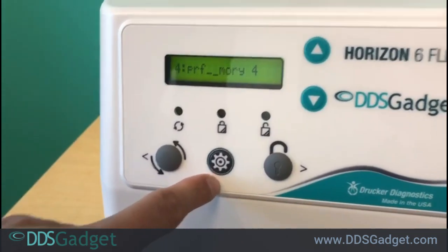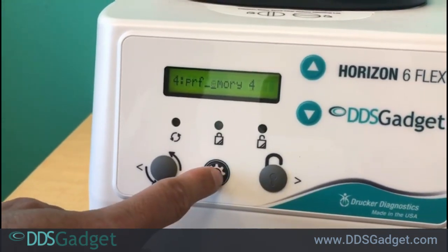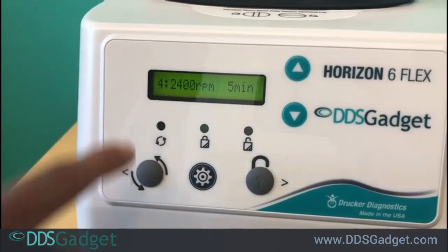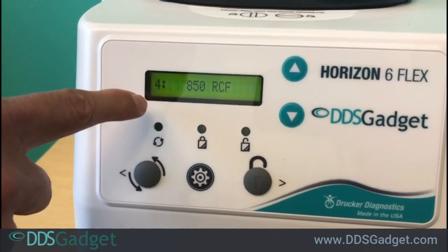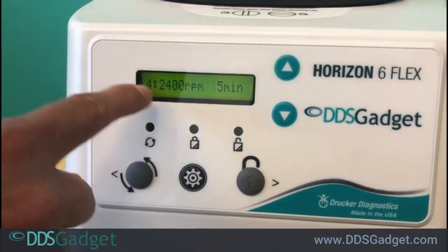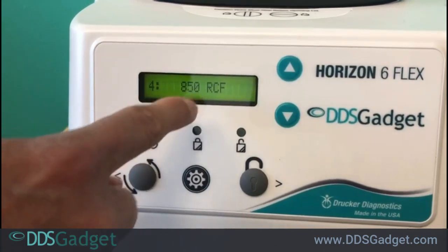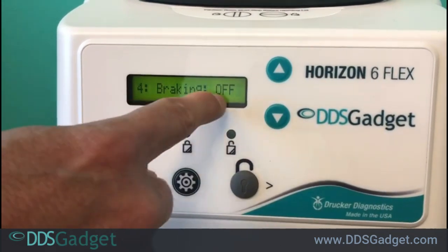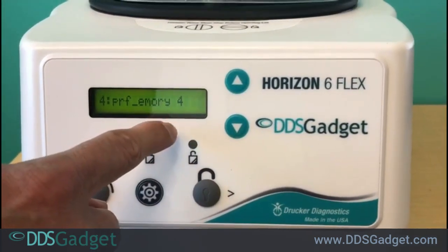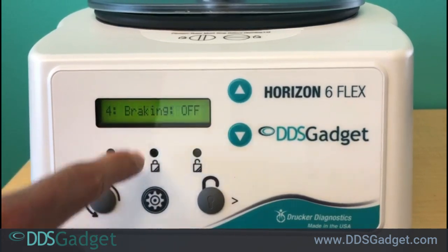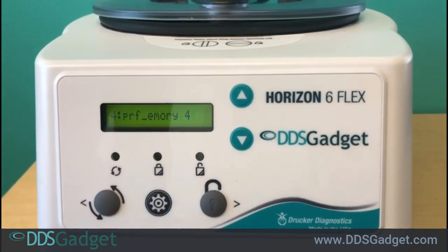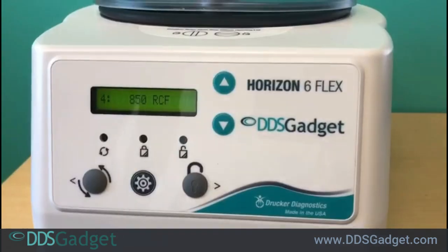Once you're done typing in all the different letters and you're happy with the name that you have, you just press the gear setting again, and that will set the cycle for you. And then you'll see that the cycle is done. It will tell you exactly all the settings in the cycle. So it has the name, PRF, 2400 RPM. Again, this is just a fake setting to show you how to use it. Braking off. And it gives you the RCF also, which is important, especially when you want to use some custom cycle and you know what RCF you need. So that explains exactly the custom setting.